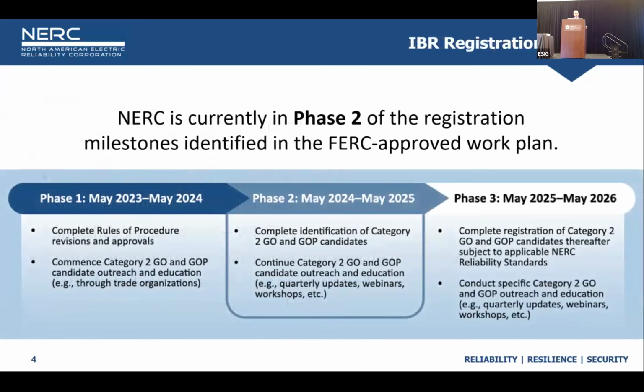But related to 901 and the standards development process as to how we got here is the recent influx of newly registered entrants to the NERC process. So that previous standards development process is tried and true, typical utility practice. If you owned a generator 75 megawatts or greater, or some of the sizable synchronous units, you were part of the standards development process. Well, this new process has a bunch of new entrants. FERC, in releasing 901, saying we need to do performance requirement changes for registered, unregistered IBR, as well as IBR, DER, in the aggregate that materially impact the bulk power system.